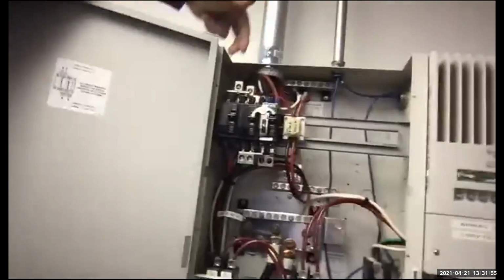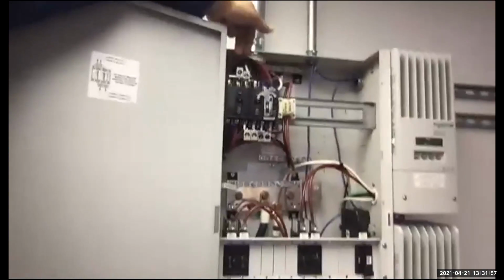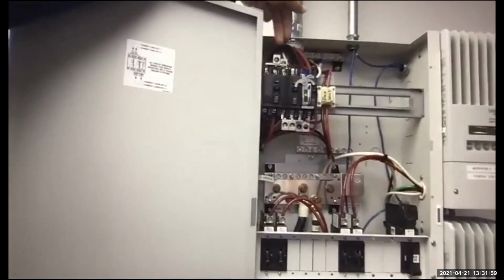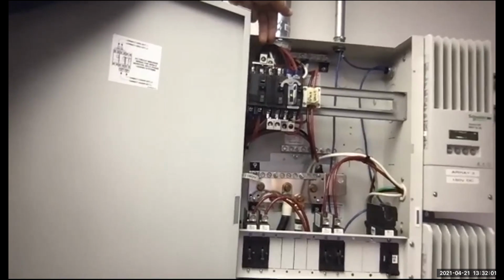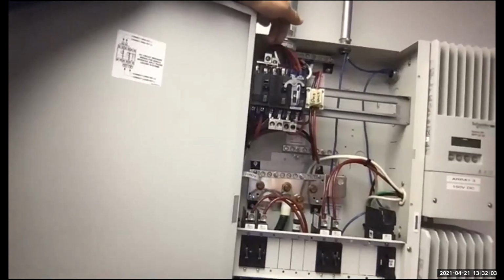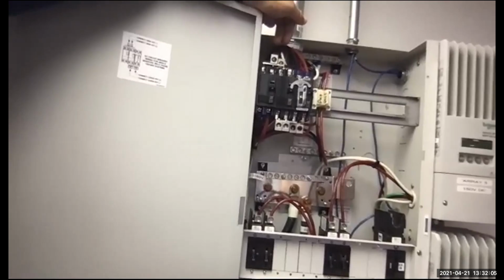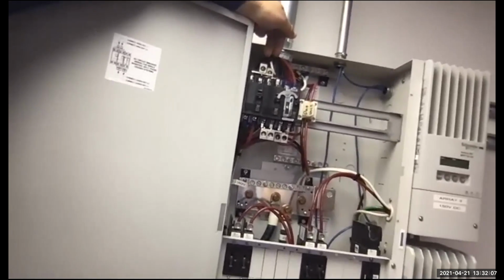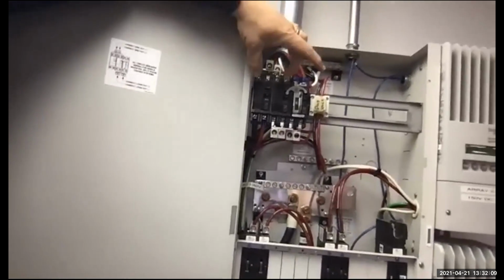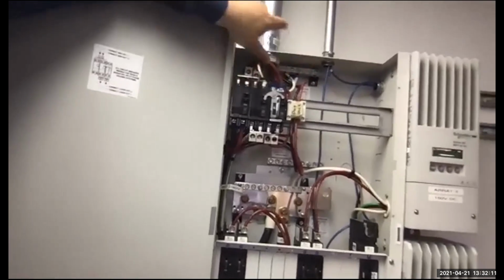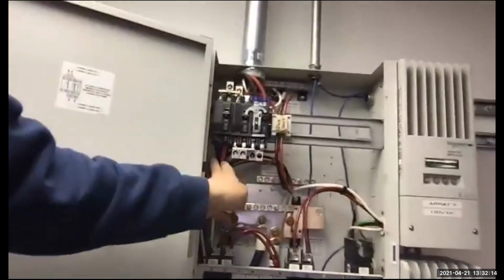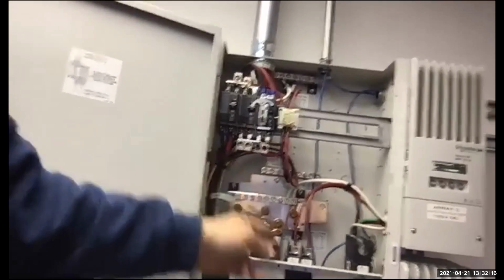We got to come in the top side, so that means we need a jumper to go between the breakers, just like this, right? So we'll have the black and the red coming in there that you already have over there. Before we go cutting wires and landing them, we just need to make sure this is built. And then we need to understand that we're going to need to bring wires from the bottom sides of that breaker all the way down and over here.